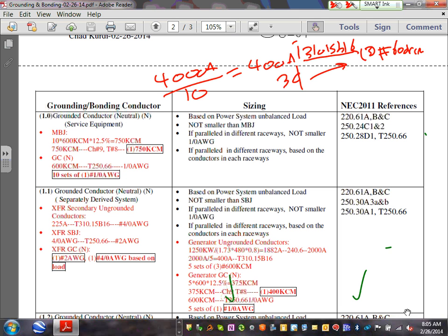Then, to size the grounded conductor, we take the 10 because we have 10 sets, multiplied by the 600 because each one of them is 600, multiplied by 12 and a half percent, you get 750. You take the 750 to chapter 9, table 8, and that will get you one conductor, 750 kcm. So your neutral, guys, can be one big fat conductor, 750 kcm. Now, there's one other problem. That's if you're putting them all in one conduit, Adam. Are you putting them in one conduit? No, we're not putting them in one conduit.